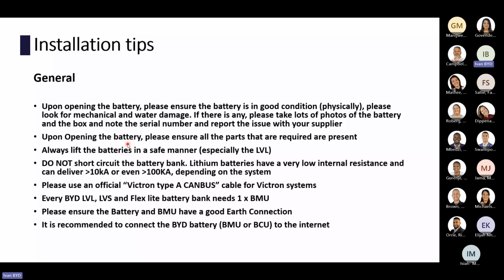Please don't short circuit the battery bank when it's running. The batteries can deliver an enormous amount of current. Please use a Victron Type A CAN bus cable for the Victron systems. The issue there is that if you're making a cable with just pin 7 and 8, your crimp doesn't sit square because it's only pin 7 and 8, and it wobbles to one side. Then please ensure your battery and your BMU have good earth connections. A bad earth connection disrupts the communications. It's rare, but once every 3 months, for example, it might go out. And it is recommended to connect the BYD battery to the internet.